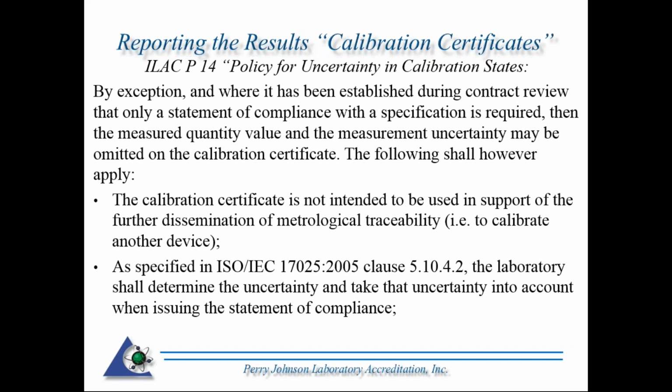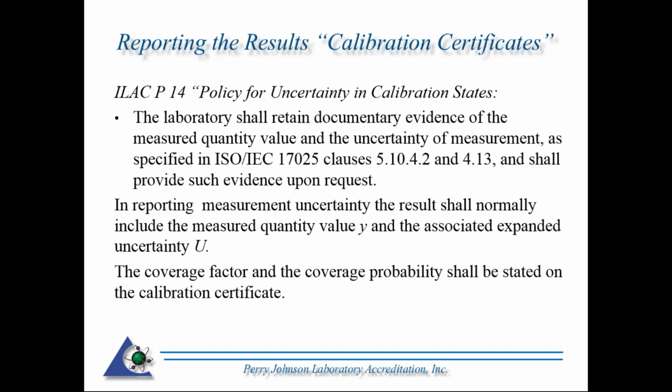So when you're making a statement of compliance within a specification, you're saying something passes or fails, you still need to know what the uncertainty is in order to make those statements. Therefore, you may not be reporting the uncertainty, but you still need to know what it is and take that into account when you're making a statement of compliance.